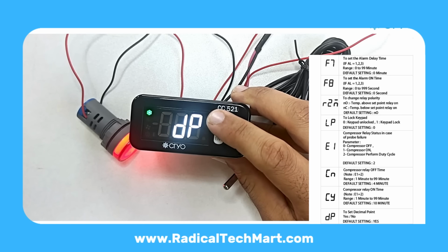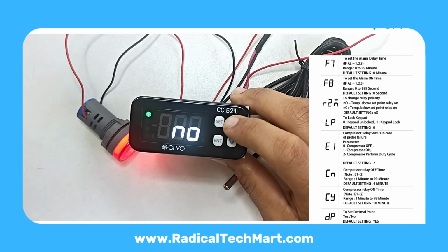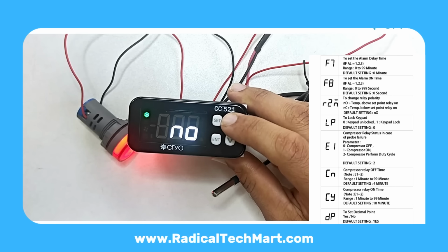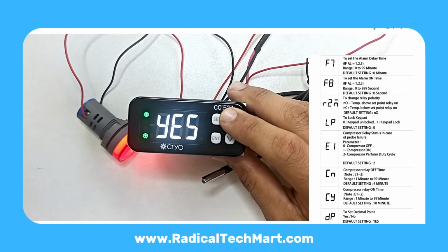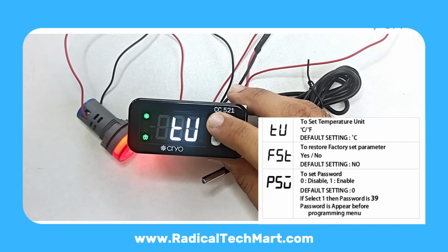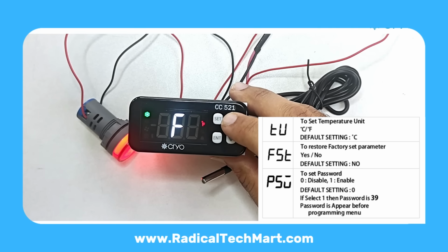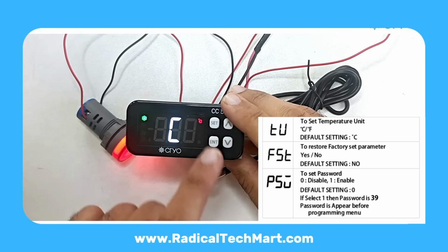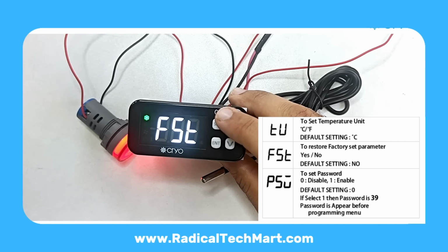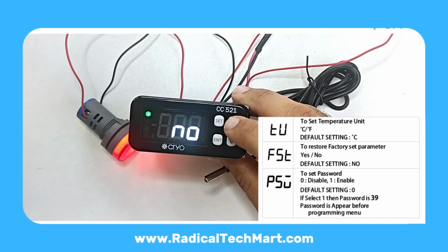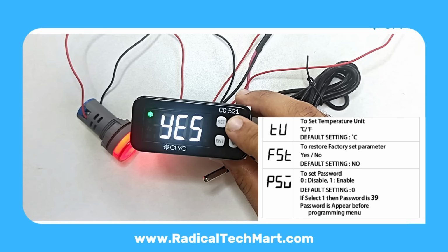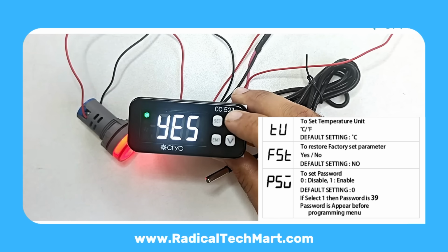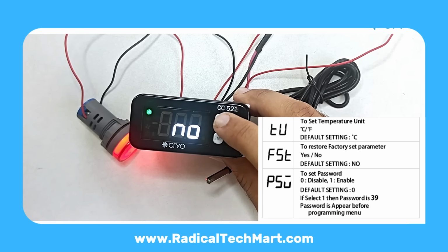Next, decimal point. Select yes to show decimal values, example 25.5 degrees Celsius, or no for whole numbers. Next, temperature unit. Choose Celsius or Fahrenheit based on your application. Next, factory reset. If you select yes and press enter, all parameters return to default. Choose no to keep your custom settings.